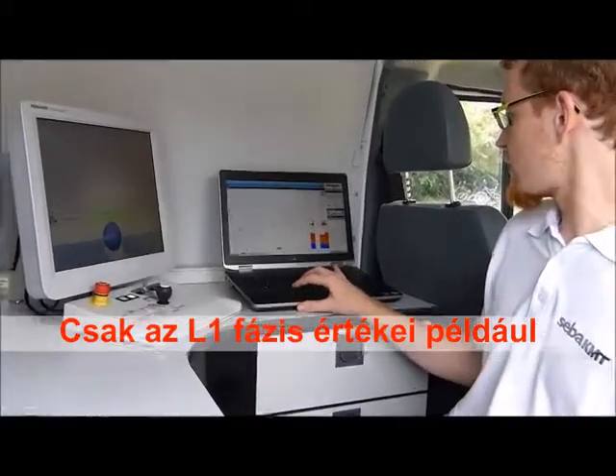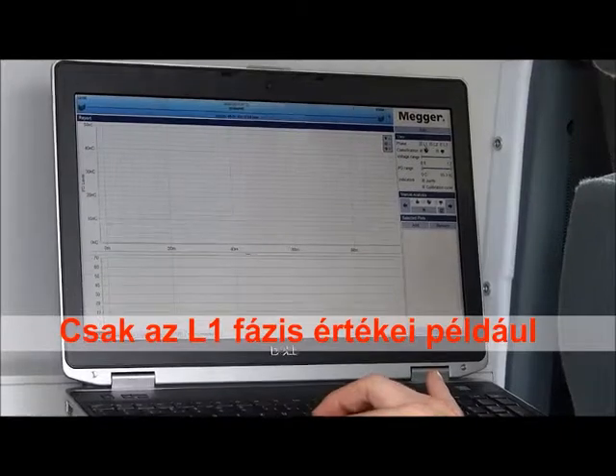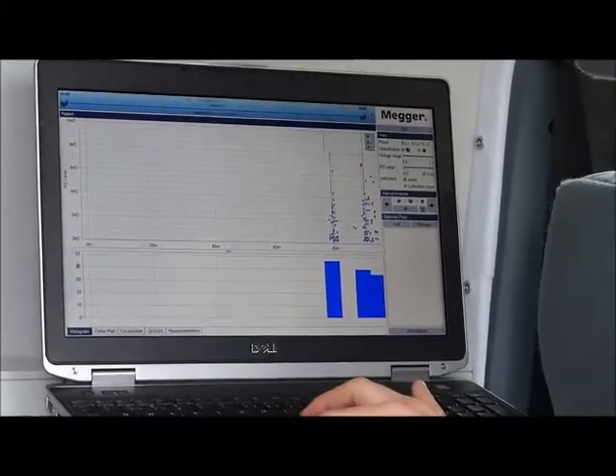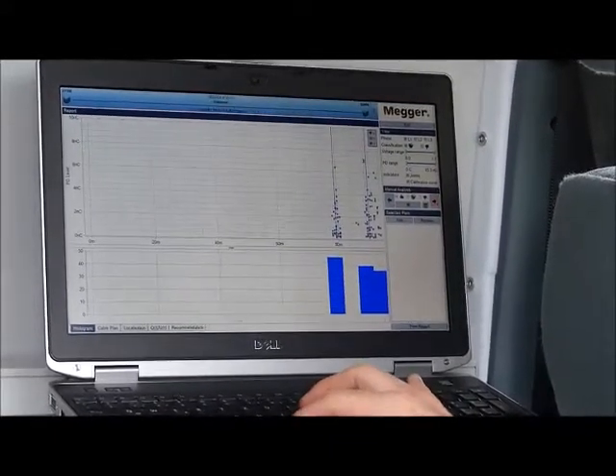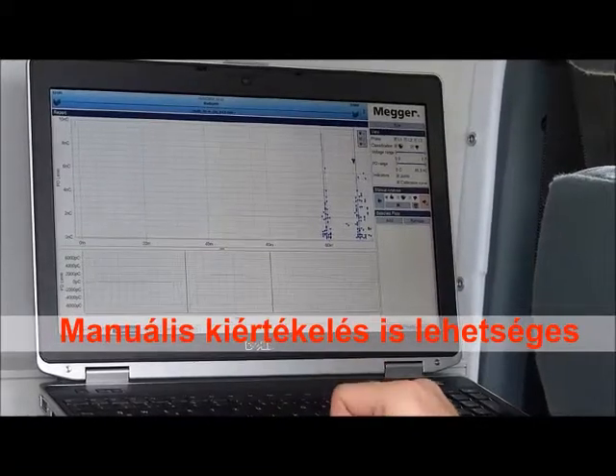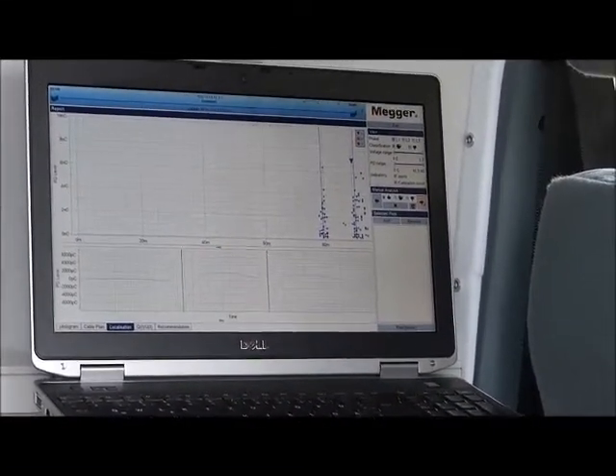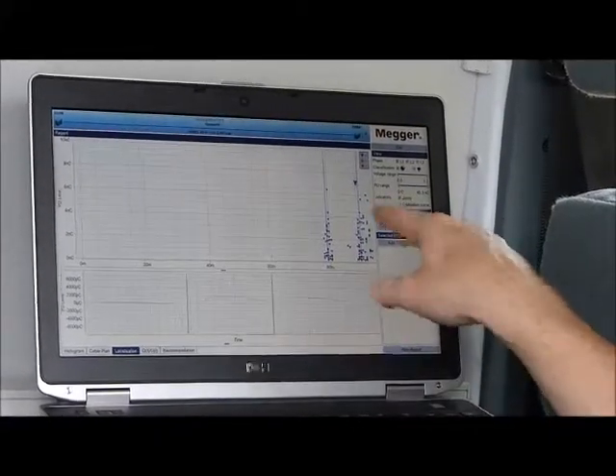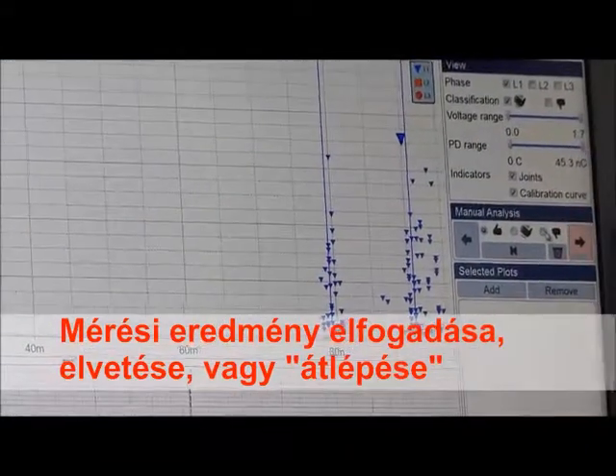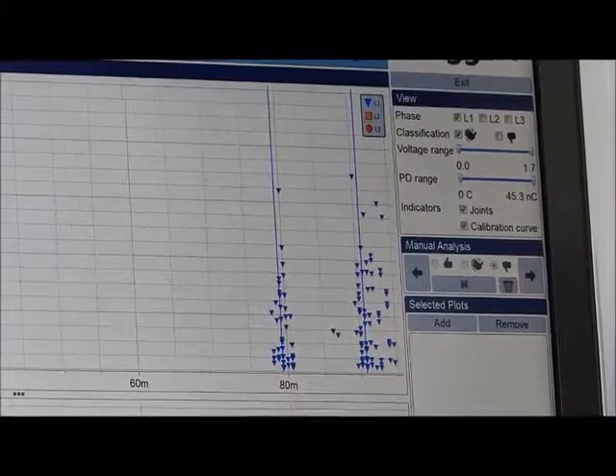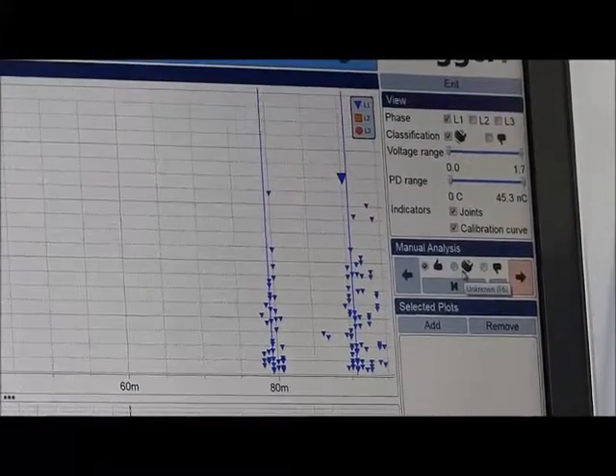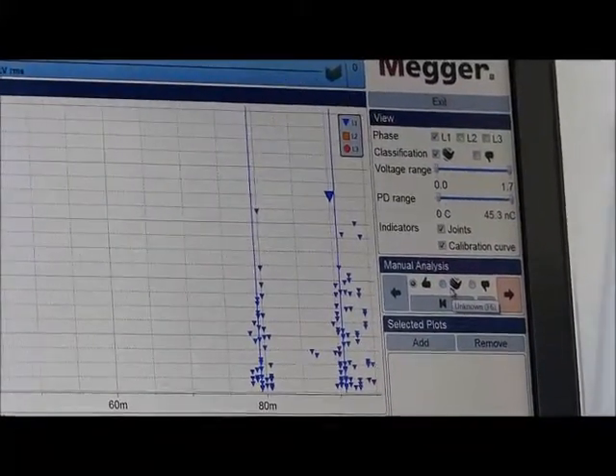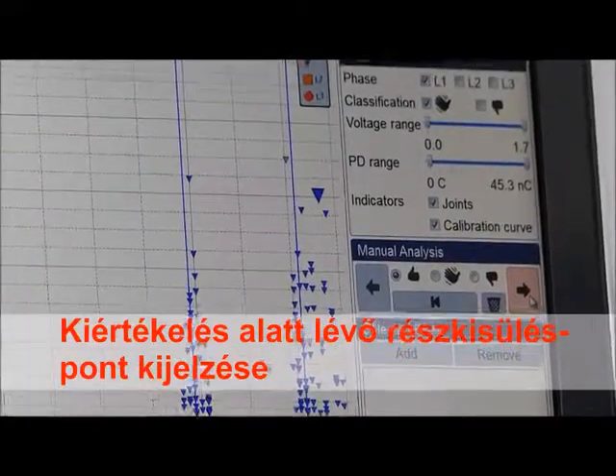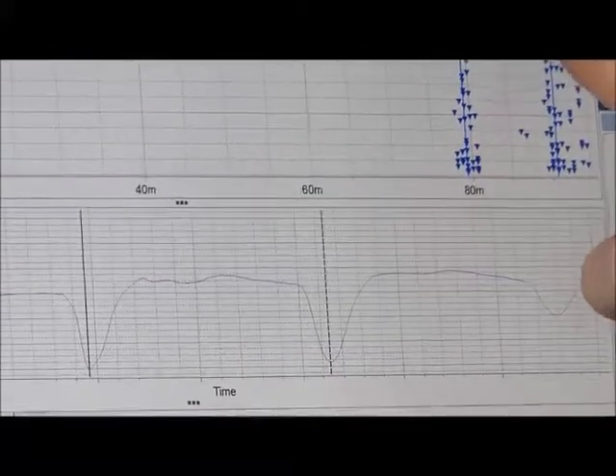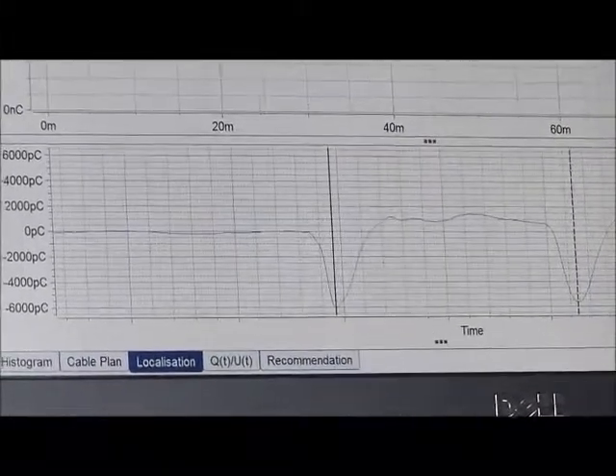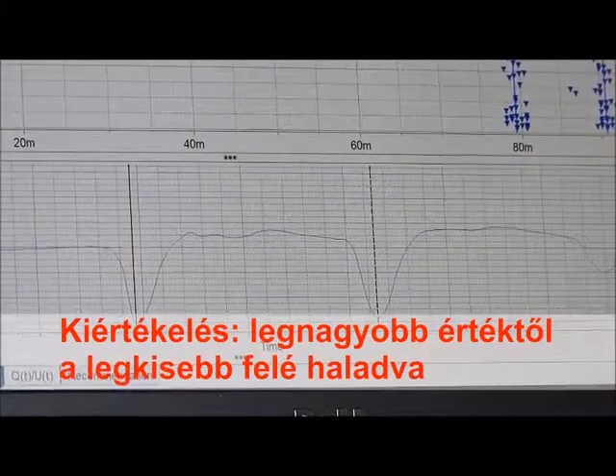So we could select, okay, we just want to see our L1 for instance. So we have roughly 50 pulses here. And we could also make the evaluation directly, also manual, if we don't trust it or we just want to agree. If you agree, okay, thumbs up. If you don't agree, thumbs down. Or if you are not sure, that means maybe it's an upcoming weak spot, then you say okay. And like you see here, it's always showing you which partial discharge you are now evaluating, starting from the highest level, going down to the lowest value.